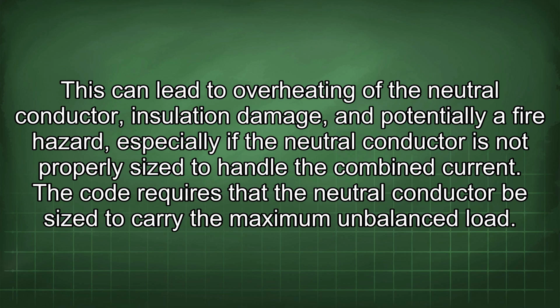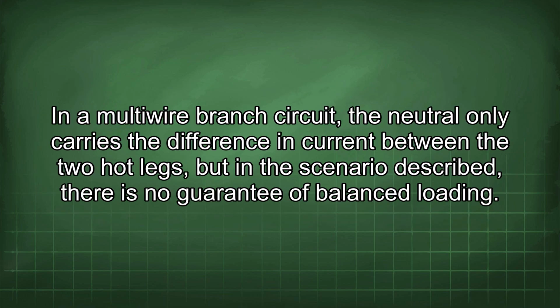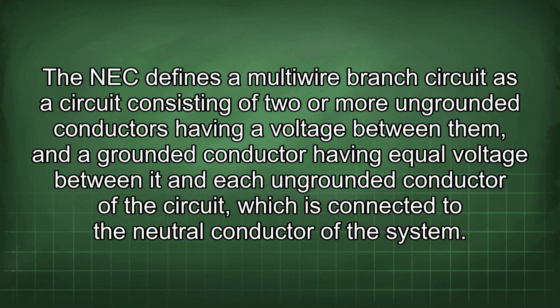The code requires that the neutral conductor be sized to carry the maximum unbalanced load. In a multiwire branch circuit, the neutral only carries the difference in current between the two hot legs, but in the scenario described, there is no guarantee of balanced loading. The NEC defines a multiwire branch circuit as a circuit consisting of two or more ungrounded conductors having a voltage between them, and a grounded conductor having equal voltage between it and each ungrounded conductor of the circuit, which is connected to the neutral conductor of the system.